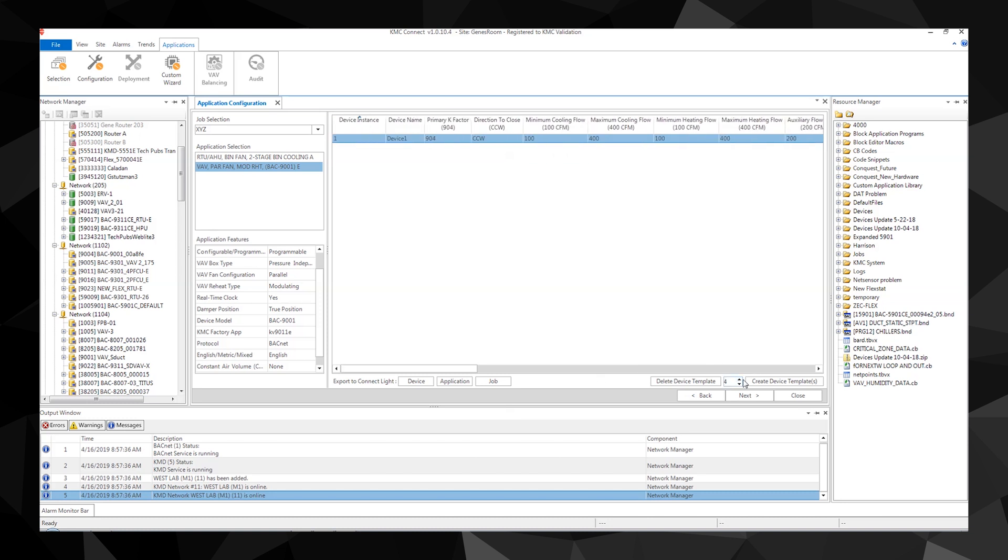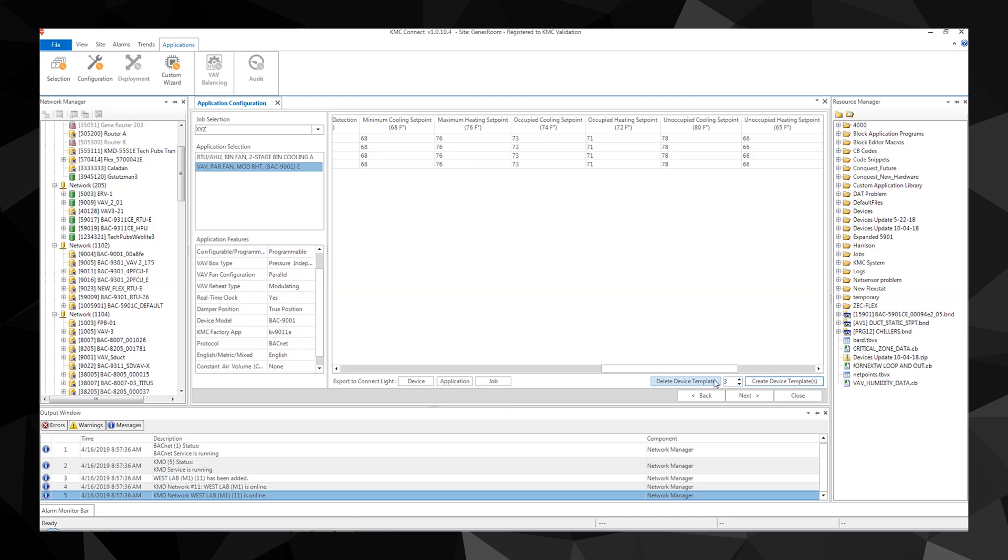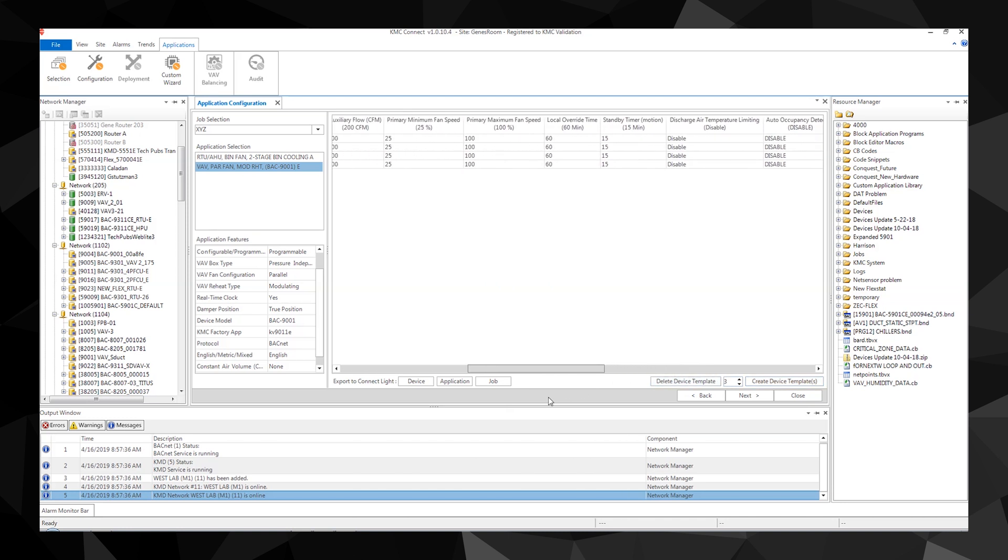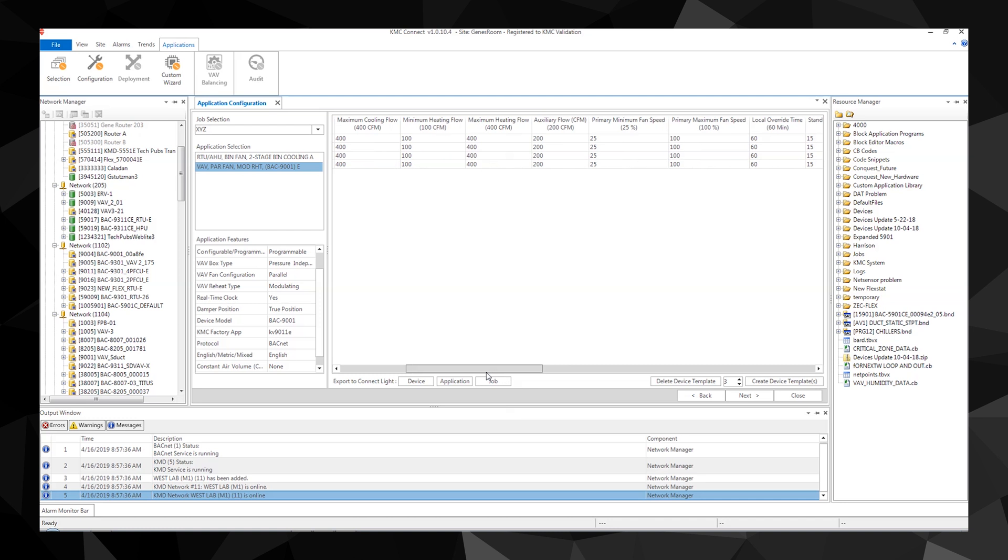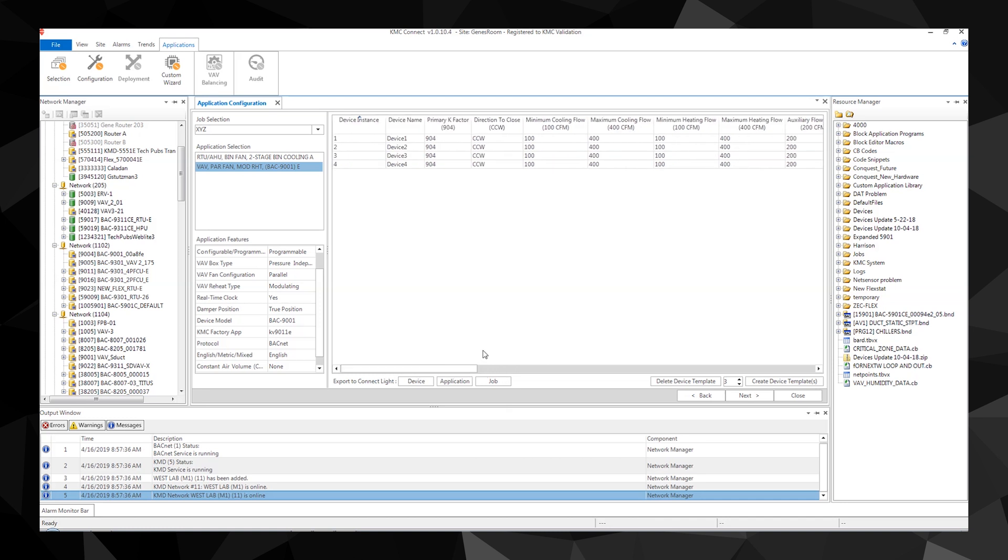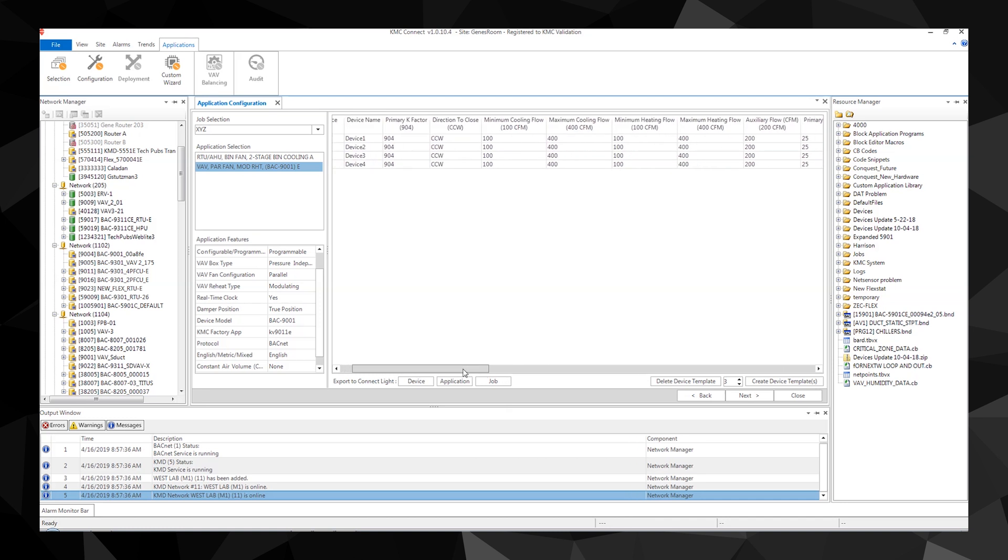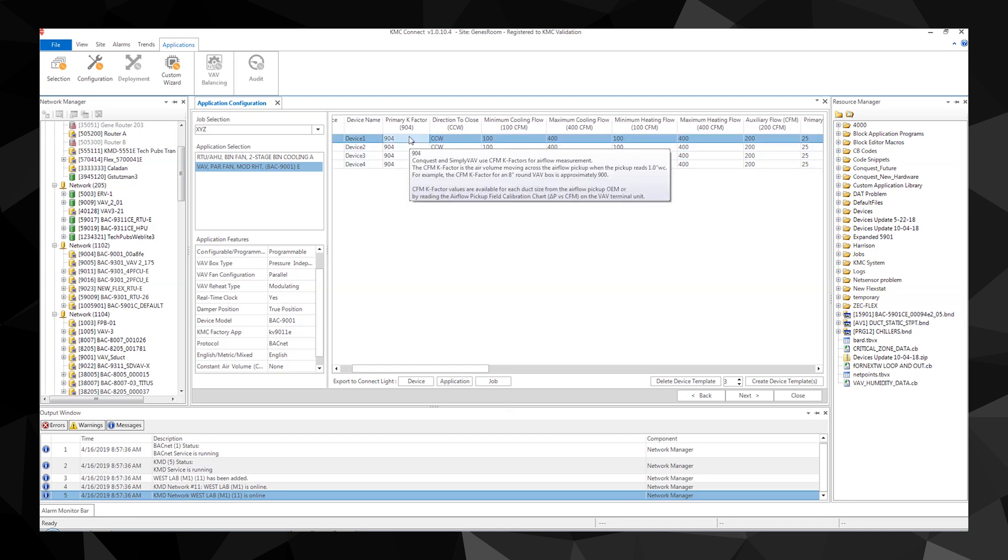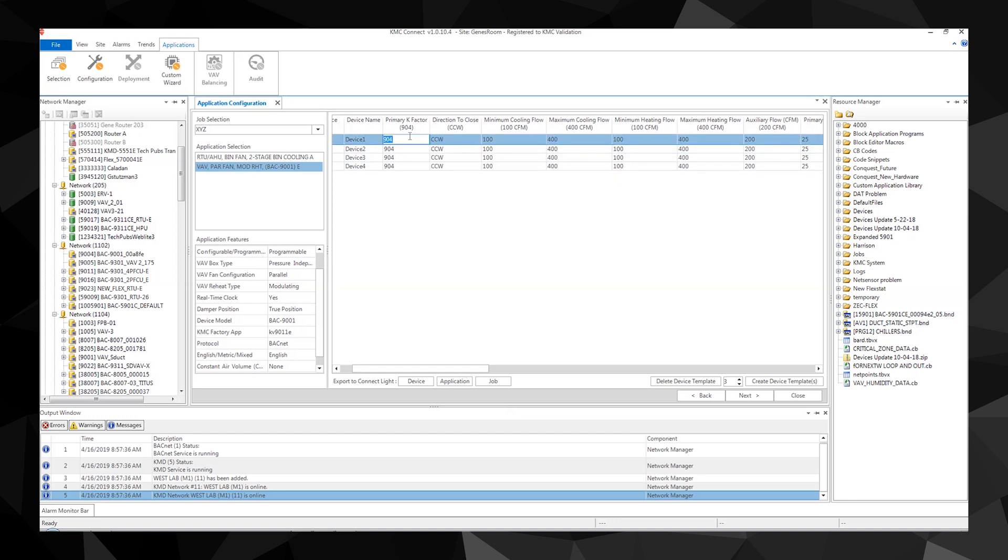Now is the time to make a clone of the template for each target controller. Let's say your job uses multiples of the same device, for example, the same model of VAV controllers, but mounted on VAV units with different K factors. You can clone the template for each size of VAV terminal unit and edit the correct K factor for each.